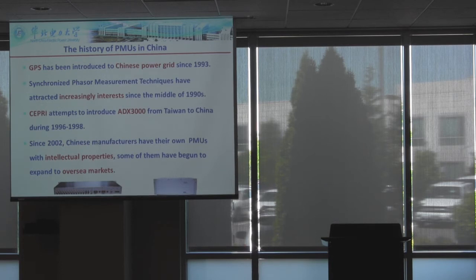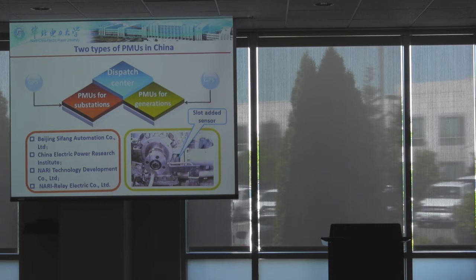Since 2002, Chinese manufacturers have had their own PMUs, and right now some of them have begun to explore the overseas market. There are 2 types of PMU in China. One, like in the United States, is for substations. The other type is for generation — they equip a sensor at the shaft of the generator and can measure the internal voltage angle directly.